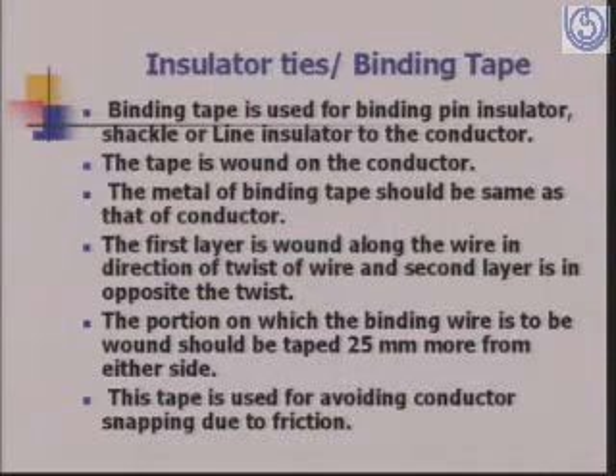Then we have the insulator ties or binding tape. The binding tape is used for binding the pin insulator, shackle or line insulator to the conductor. The tape is wound on the conductor. The metal of the binding tape should be same as that of the conductor, otherwise there will be bimetallic reaction. So therefore the metal of binding tape is used as the same as that of the conductor.